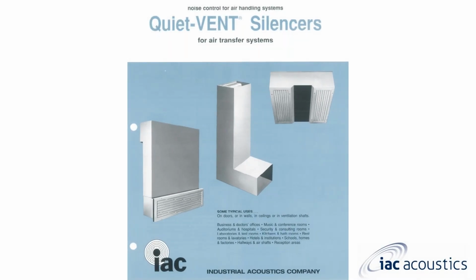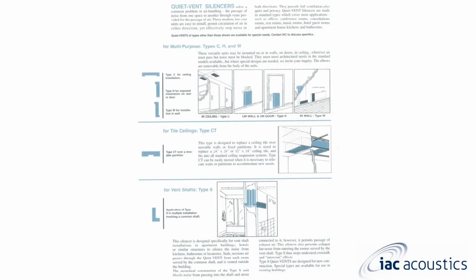Our quiet vent silencers, also known as air transfer systems or crosstalk silencers. Here you can see, for example, the type CT is designed to replace the ceiling tile over movable walls or fixed partitions. You can also use type C, H, or W in a wall, in a door, or in a ceiling. Type S are vent shafts.